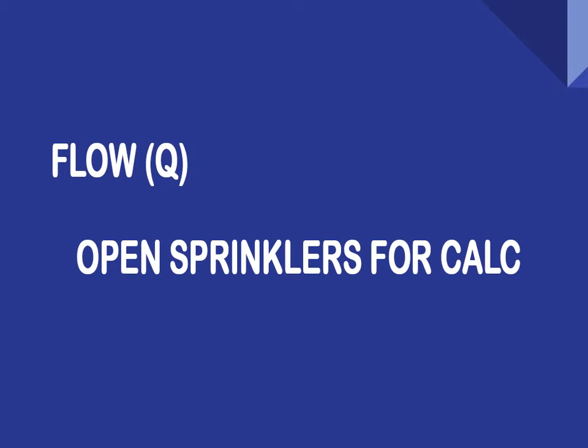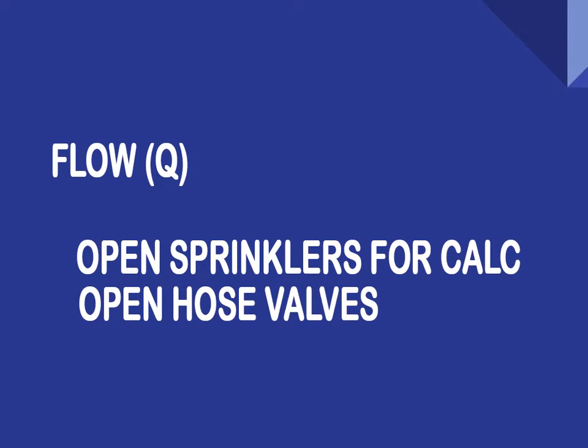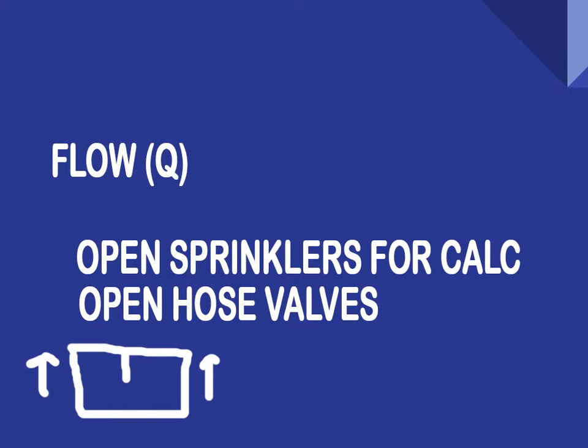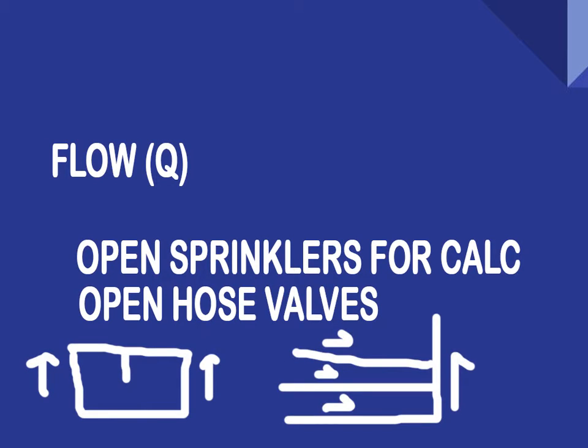Let's look at the three factors we listed. First off, we had flow, which is the biggest contributor since the other two can actually be mathematically converted to even out, something you just can't do for flow. Anytime we add flow, we are increasing our friction loss across pipe length. So that means that any heads flowing in a remote area add flow and thus get nodes, as well as any open hose connections and/or allowances. This also changes where flows combine, such as in loops or grids. These nodes make up the bulk of our reference points.